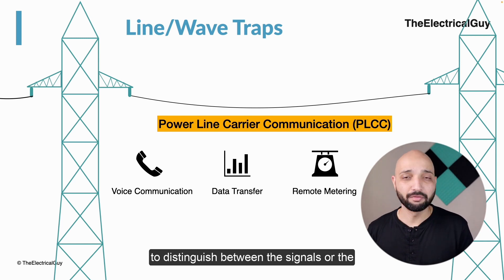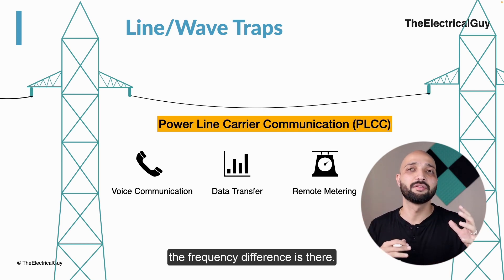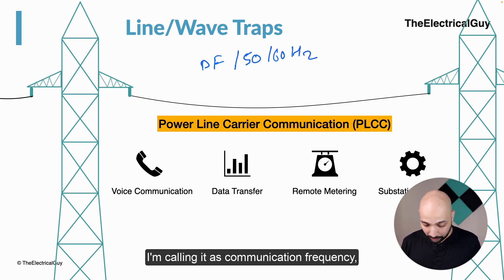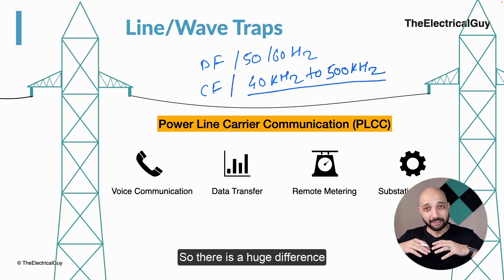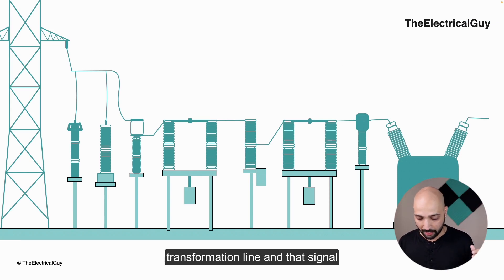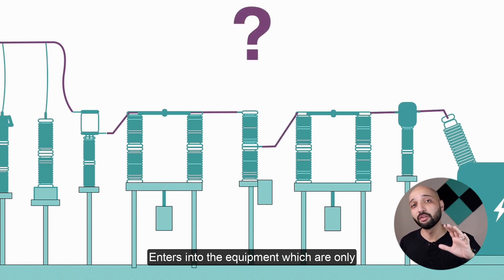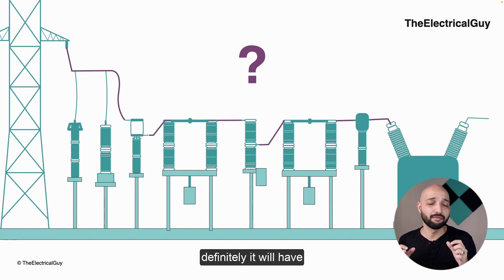To distinguish between power frequency current and communication signals, there is a frequency difference. The power frequency signal operates at 50 or 60 hertz, whereas the communication frequency may vary from 40 kilohertz to 500 kilohertz. There is a huge difference between these frequencies, and if you are transferring communication signals via the transmission line, that signal can enter into substation equipment which is only designed to carry 50 or 60 hertz.